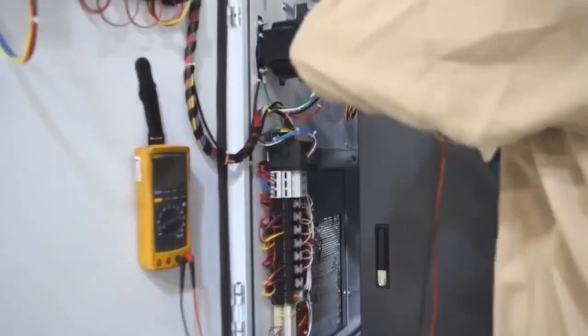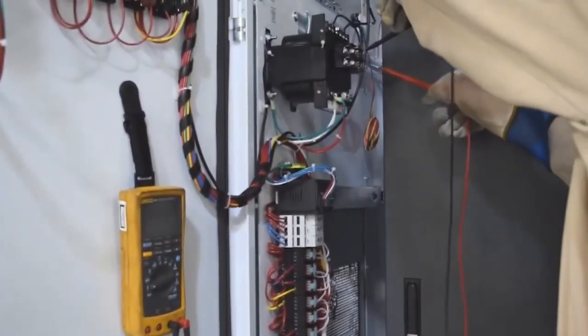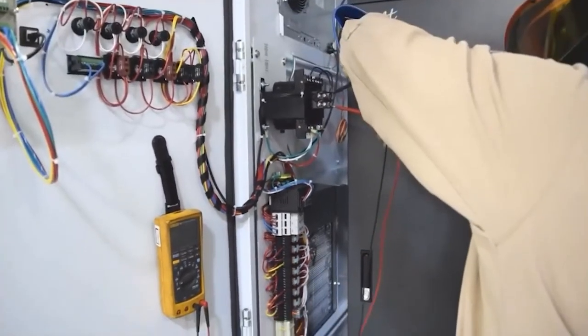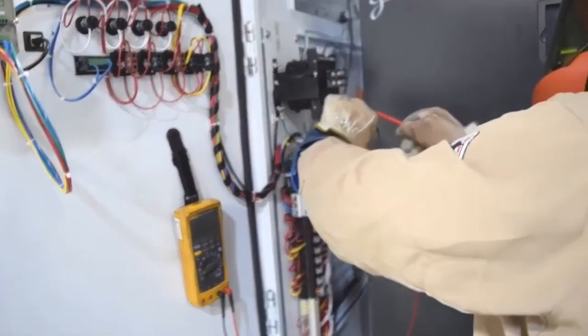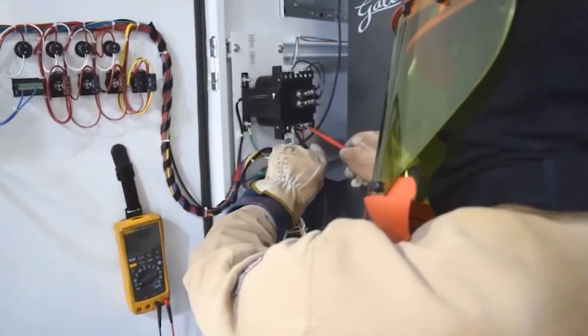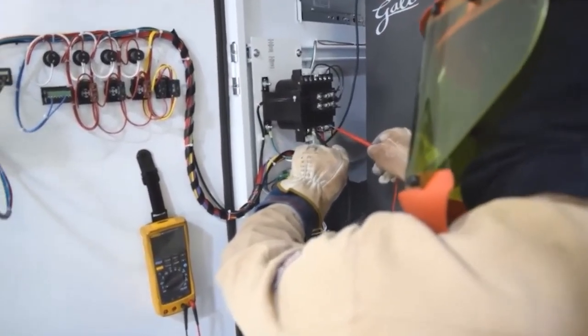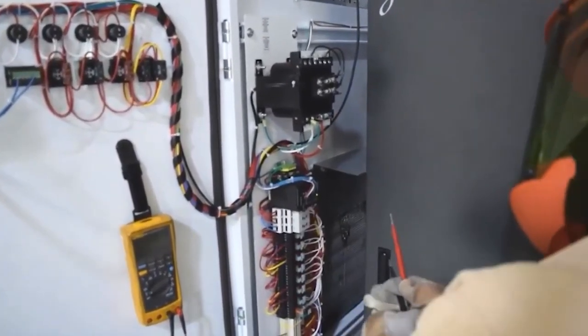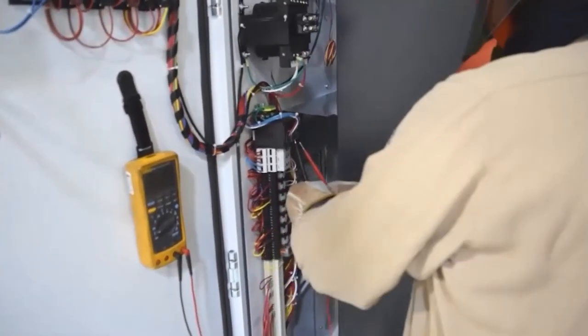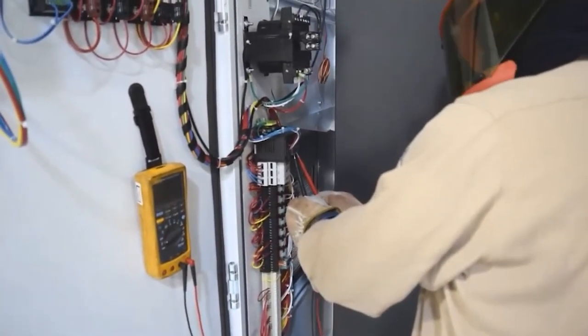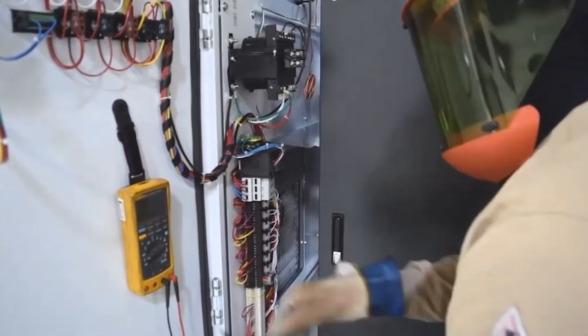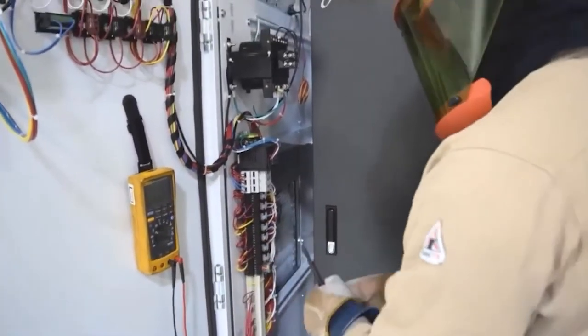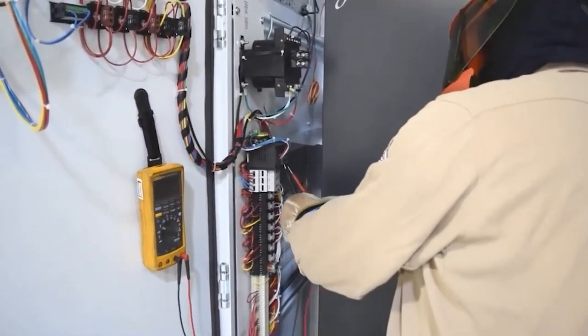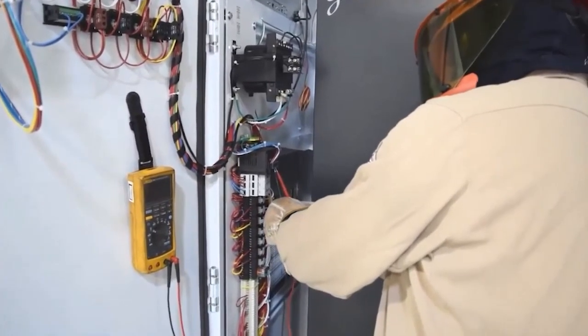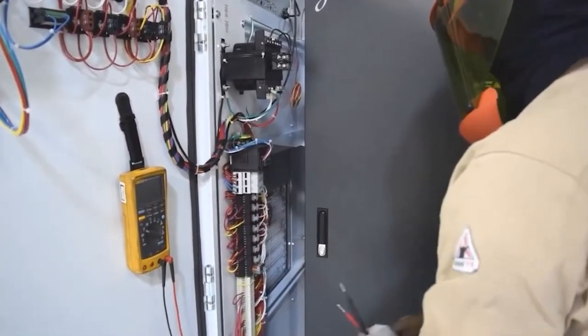So now I'm going to move over to my control power transformer. I'm going to measure my primary and my secondary of the fusing just to make sure I got all my power coming to it, as well as I got all the proper voltage coming out of it. And then since this cabinet has a power supply, I'm going to go ahead and measure the 24 volt output as well as the AC input. Make sure that I got proper voltages everywhere I should have them.